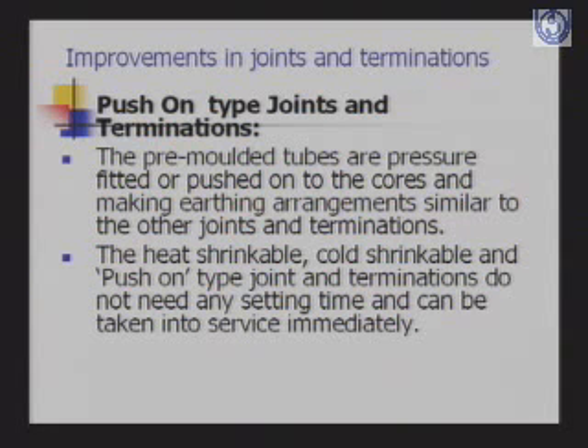and terminations. The heat shrinkable, cold shrinkable and push-on type joints and terminations do not need any setting time and can be taken into service immediately. The epoxy resin type of joint and termination requires some setting time for the epoxy to get hardened, but these types do not require any setting time.